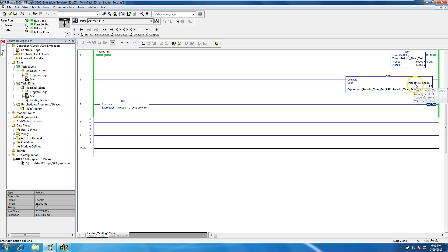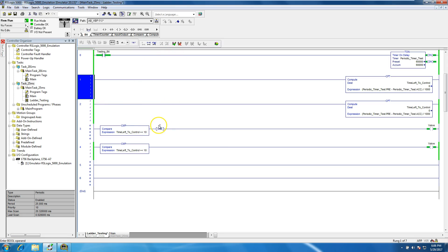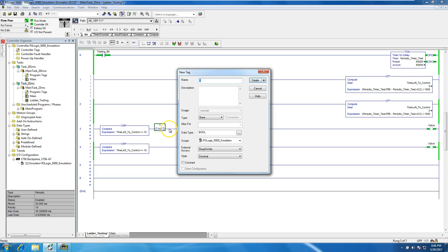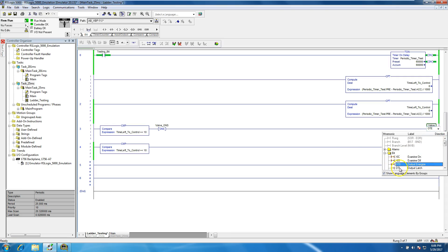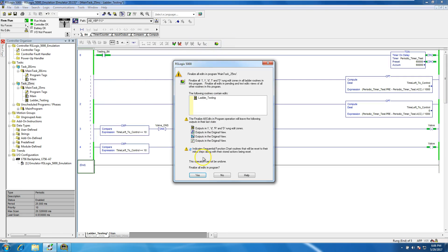Anytime the time left is below 10 seconds it will cut on. What we can do is put a one-shot in there — we'll call it 'valve on' — and then we'll turn the output into a latch. Let's delete those rungs so we can assemble it. That's a latch, so if we take it off it's still going to remain latched and stay on.